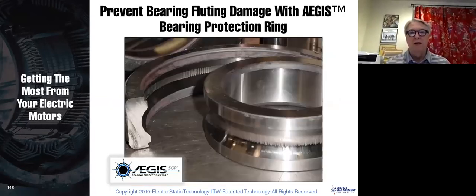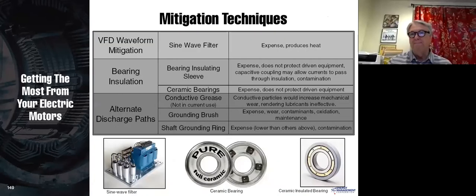Here is the inner race and the outer race. Whenever you get a motor that's run on a VFD, and you take it to a motor shop for repair, they should always cut the bearing. Make sure that they do that. Cut the bearing, wipe the grease out, and inspect for damage here.